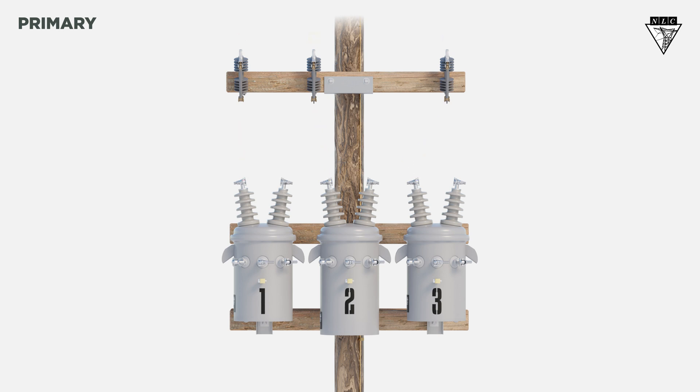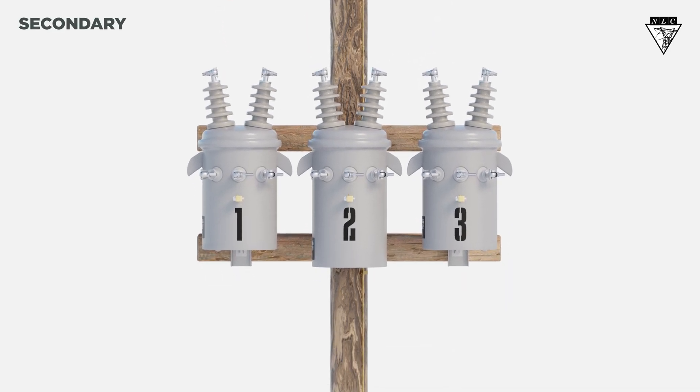Let's move on to the secondary side to complete the connections. Our secondary coils are connected in series. To configure the delta secondaries, first bond all transformer cases together and tie them to ground. Then we'll connect the lighting transformer's X2 bushing to the neutral.